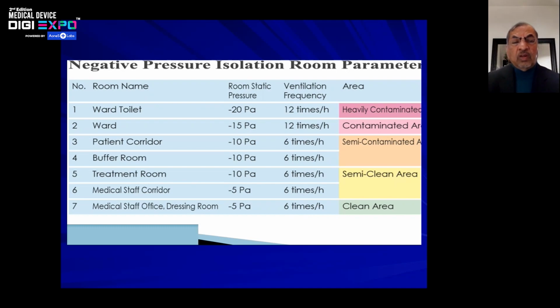And for negative pressure isolation rooms, we have also issued a guideline in which the ward toilet can have the highest room static pressure of minus 20 Pascal with a ventilation frequency of 12 times per hour, as it is heavily contaminated. Wards can have minus 15 Pascal with 12 times per hour as a contaminated area. The patient corridor, buffer room, and treatment room can have minus 10 Pascal with 6 times per hour ventilation frequency. And the medical staff corridor, medical staff office, and dressing room can have minus 5 Pascal and 6 times per hour. These are relatively clean areas.